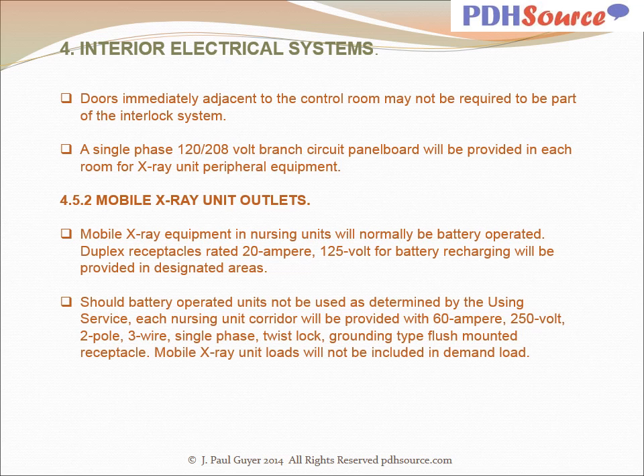Should battery operated units not be used as determined by the using service, each nursing unit corridor will be provided with 60 amp 250 volt two pole three wire single phase twist lock grounding type flush mounted receptacle. Mobile X-ray unit loads will not be included in demand load.